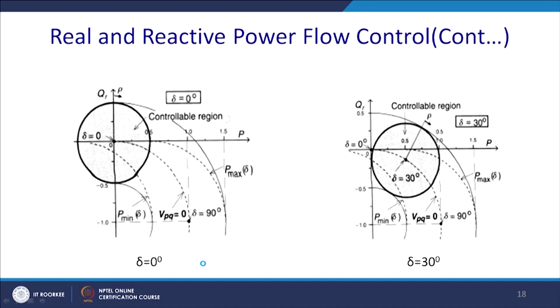This is the case of delta equal to 0 degree, and you see that there is a unit circle and this is a controllable region, and thus, this is the case of the line where Vpq is 0. So, you will have this line, and ultimately this circle will move like this if you change the value of delta. Similarly, what happens if you make delta equal to 30 degree, so the real power will be 0.5 and the reactive power you can calculate. So, it will shift to this point and this circle will be coming like this.